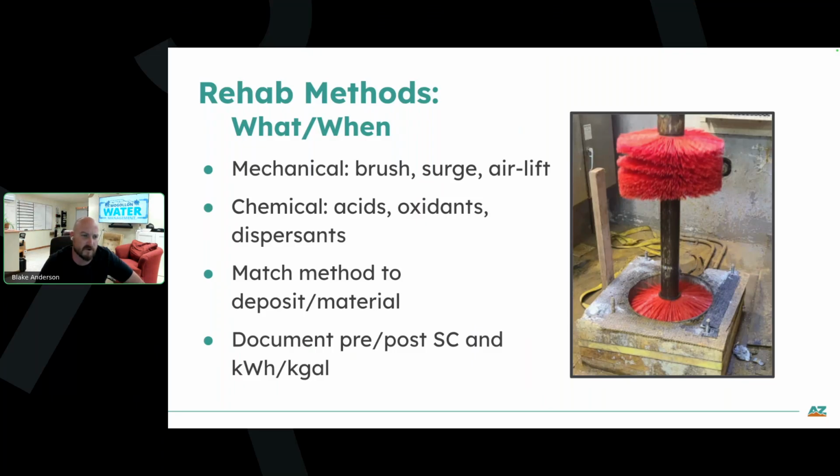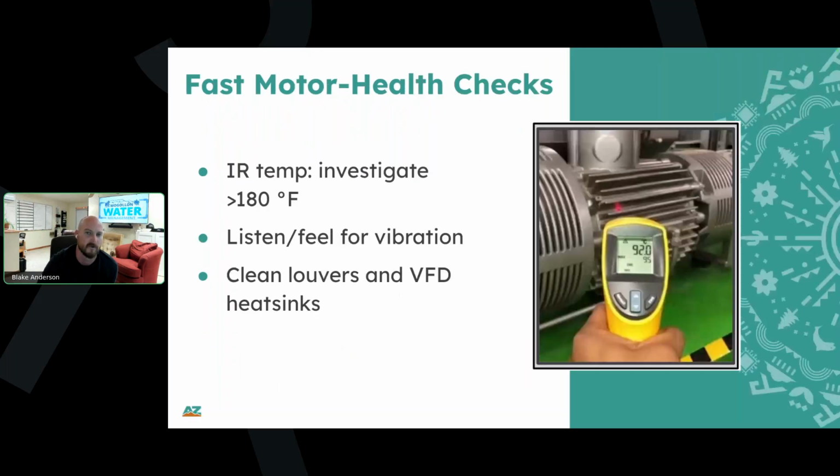And then after you're done rehabbing stuff, reset that baseline for your specific capacity, reset your kilowatt hours per 1,000 gallons, and especially if you can show a big change, like I talked about that 700% energy efficiency, share that with your management. Be able to document and share the wins and the successes and why it's worthwhile to take the time to do things right and invest in maintaining the assets, not just building new ones.